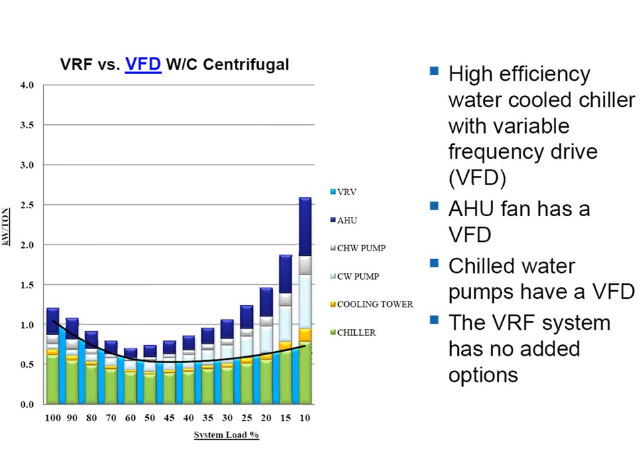The majority of systems that I've worked on have natural ventilation systems. Now, I'm not a fan of natural ventilation at all. In fact, I'm sort of opposed to it. But a lot of the VRF systems that I personally have worked on were going into buildings that have heating-only steam or hydronic radiators, and we're adding cooling systems, and they're currently permitted under codes that have natural ventilation, and they're keeping the natural ventilation. Right? So that's one of the reasons. Now, I'd argue that hardly anyone opens their window, but that's a separate debate. But good point, Jonathan. This chart on the screen did not include ventilation costs on a VRF system.